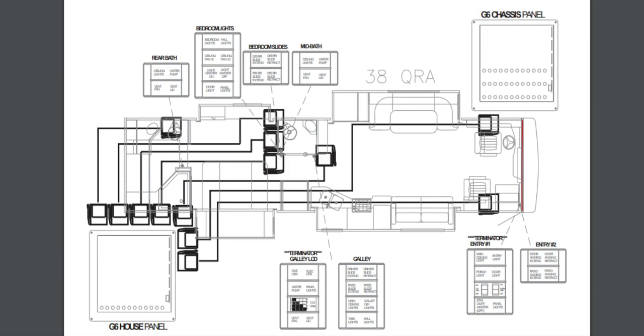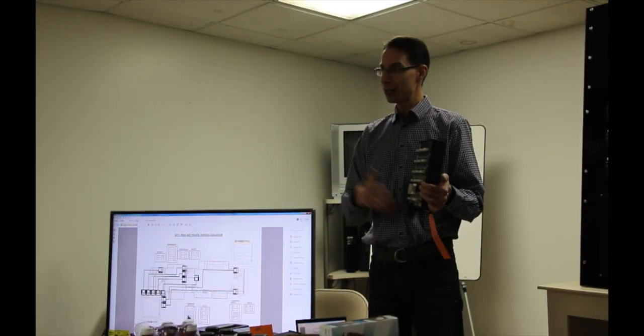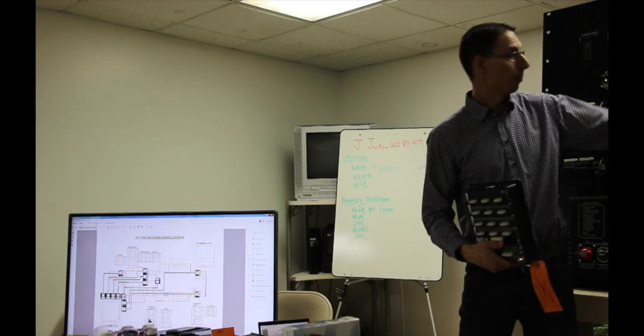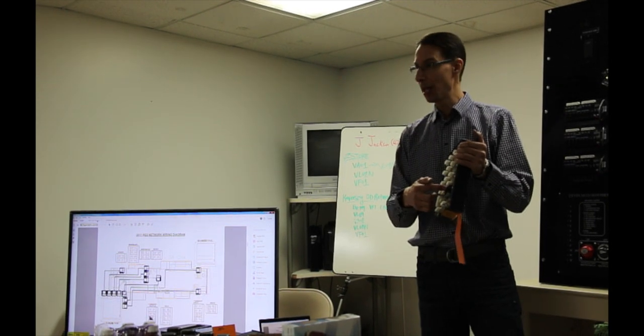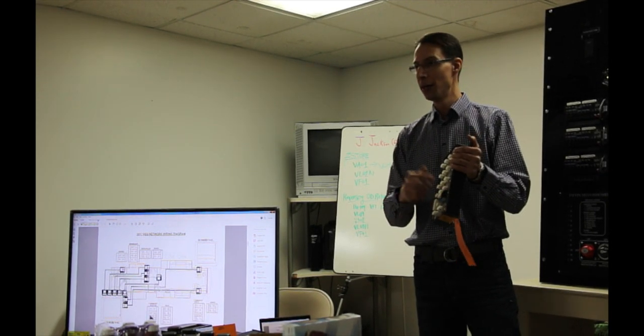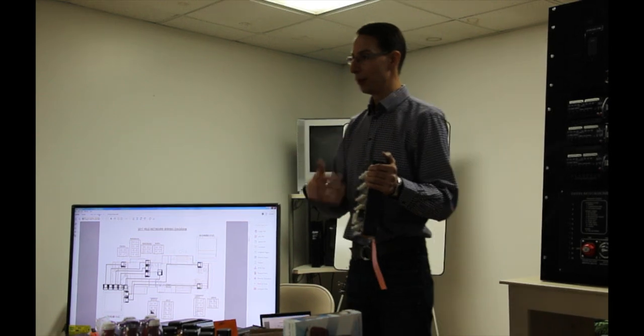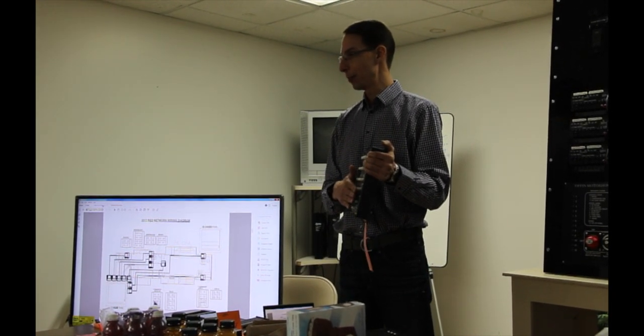Now this is really important to understand because some people think maybe it's important that the connector plugs back into the exact same location. There's like 12 slots here. That doesn't matter. Again, it's the party line system. Whether I take this keypad and plug it in somewhere else or I plug the network cable from here to here, that doesn't matter. You don't need to worry if you have to unplug some of them, oh man I got to plug them in exactly the same place again.